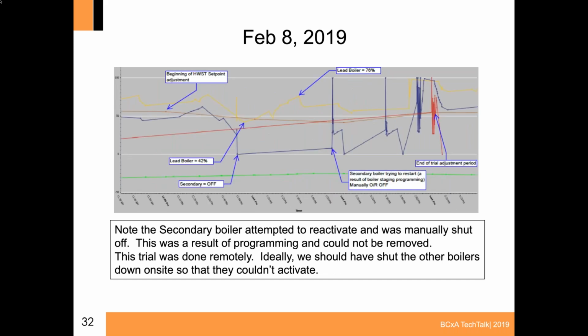So this is the actual trial period. You can note there's 2 times when the secondary boiler tries to restart, and this was a result of that programming where it's looking at a temperature differential and trying to bring it back on. So while this was going on, we actually had to override it to get it back off because we wanted to see if one could handle the entire load. The actual outdoor temperature at that time was around minus 25 Celsius, which was pretty cold.